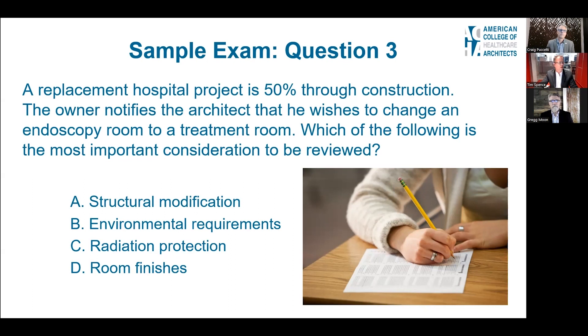We know there's no discussion about what's actually taking place in that treatment room related to radiation. So we're down to environmental requirements and room finishes. Environmental is going to be the answer because we're going to need to check pressure requirements, outdoor air change requirements, and minimum total air change requirements.